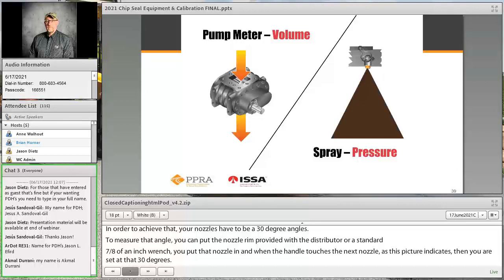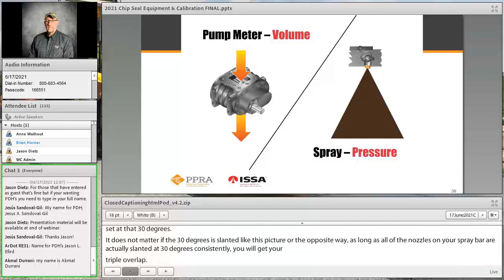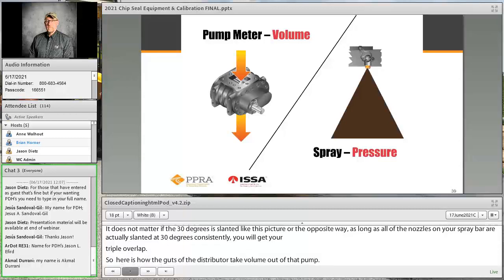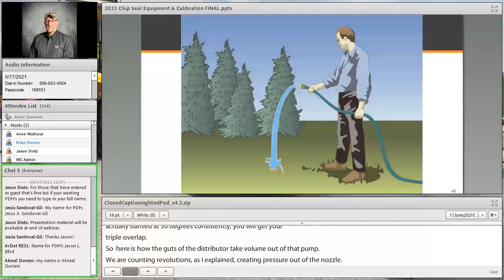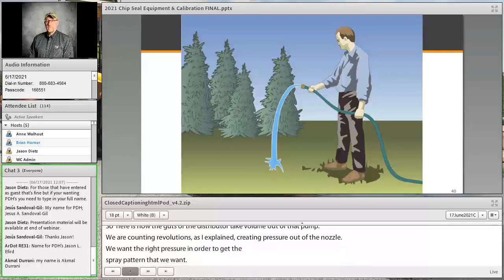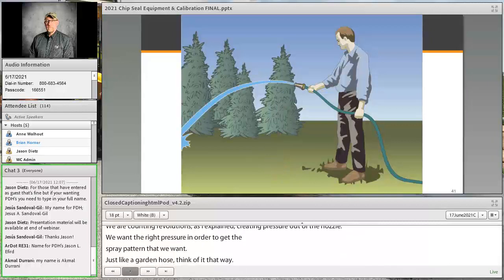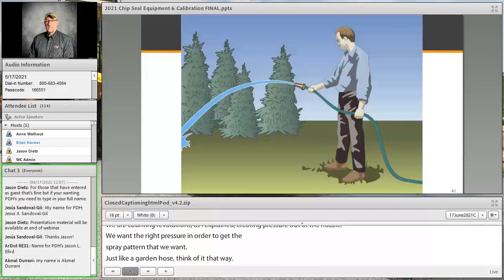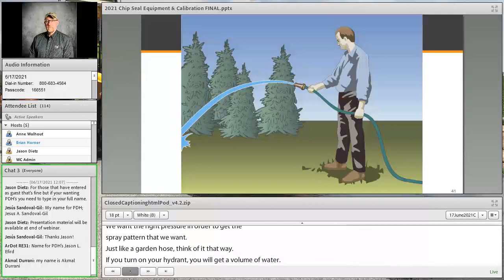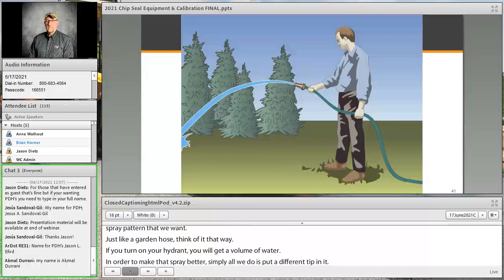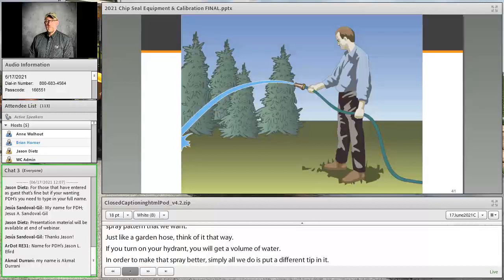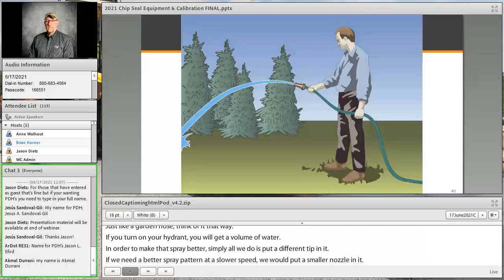So here's how the guts of the distributor take volume out of that pump. We're counting revolutions, as I explained, and creating pressure out of the nozzle. We want the right pressure to get the spray pattern we want. It's just like a garden hose -- think of it that way. If you turn on your spigot or hydrant, you're going to get a volume of water. To make that spray better, all we do is put a different tip in it. If we need a better spray pattern at a slower speed, we'd put a smaller nozzle in. If we're going really fast, or using a lot of oil, we might put a bigger nozzle in. So we're actually taking the volume and adjusting the pressure by changing the size of the nozzle itself.